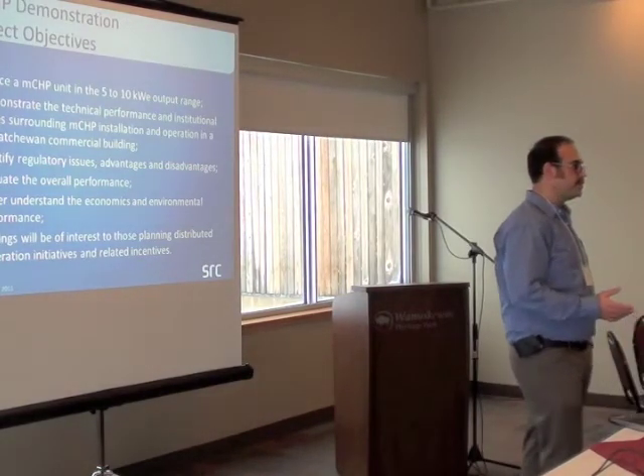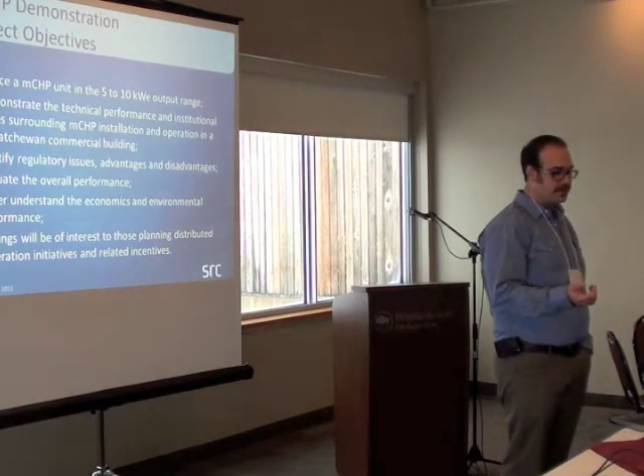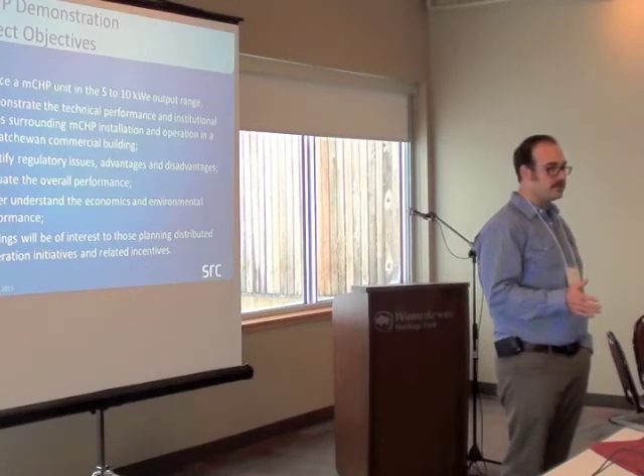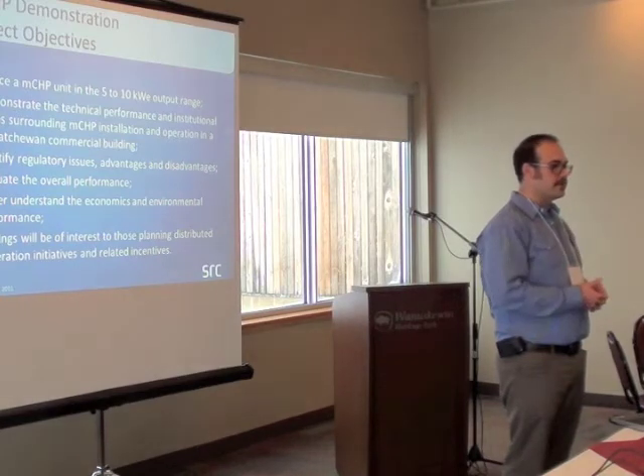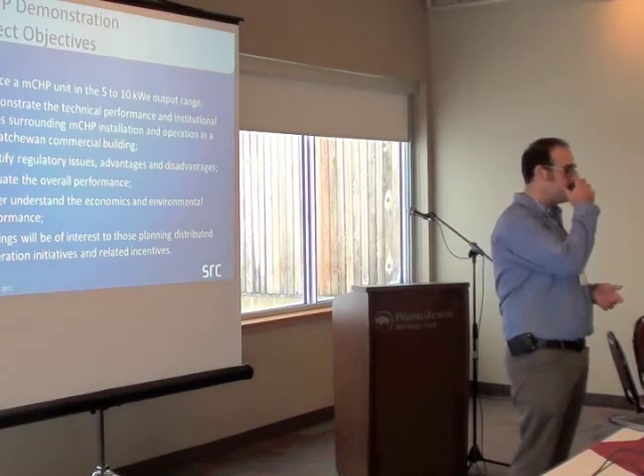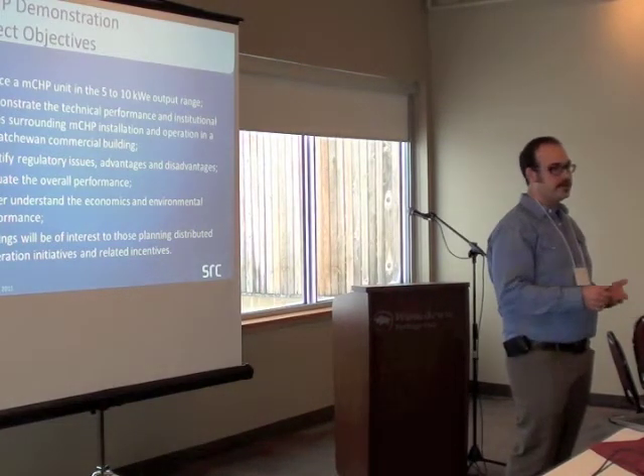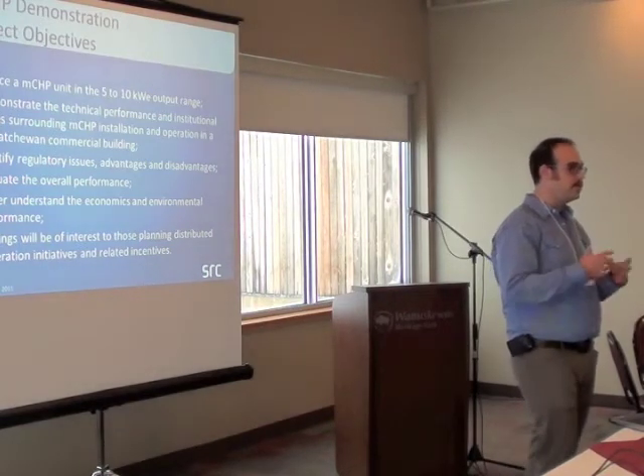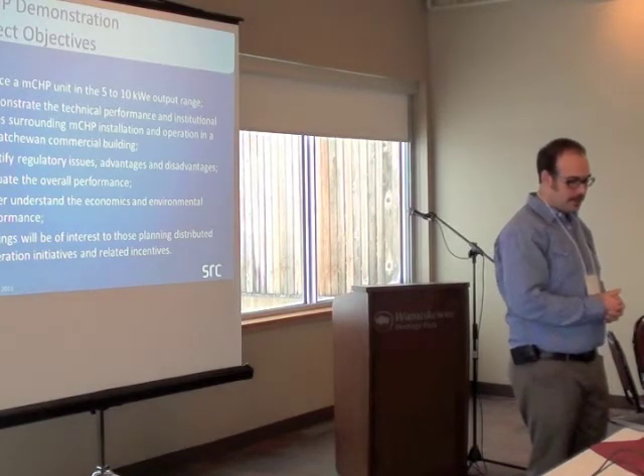So for our demonstration project down in Regina, we tried to source a micro CHP unit in the 5 to 10 kilowatt electric range. We wanted to demonstrate the technical performance, how efficient it is, and what kind of barriers there are to the installation of this system. This is new technology to Canada, definitely new to Saskatchewan, and the code officials don't know how to deal with it, the building owners don't know how to deal with it, utilities don't know how to deal with it. So we wanted to go through, document how we installed it, where we felt there were barriers, and how we can overcome those.